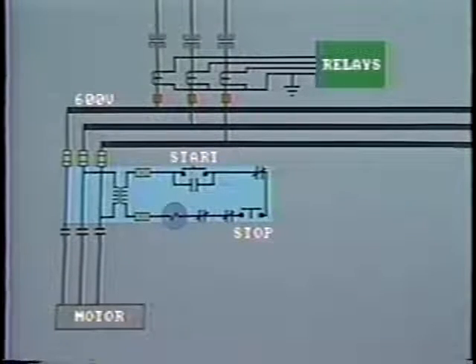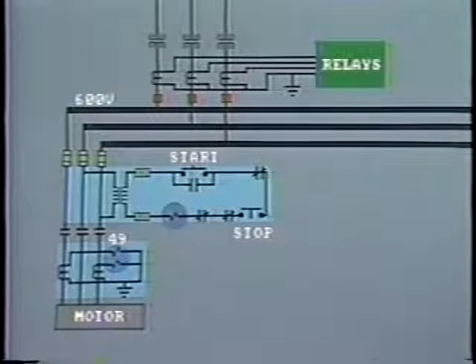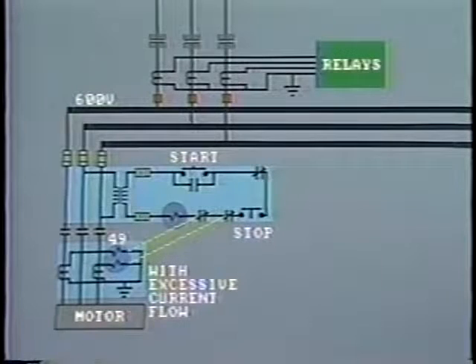First, overload protection. CTs in the supply leads measure stator current with the secondary feeding a thermal relay, number 49. The thermal relay provides overcurrent protection. It consists of a heater element which operates a bimetallic switch. Excessive current flow will cause the switch to open and so interrupt the power supply to the contactor coil. Now, although we definitely want this relay to trip to prevent overheating of the motor, we certainly do not want it to trip for low-level, permissible overloads. So the relay must be chosen and set to match the thermal limit curve of the motor.